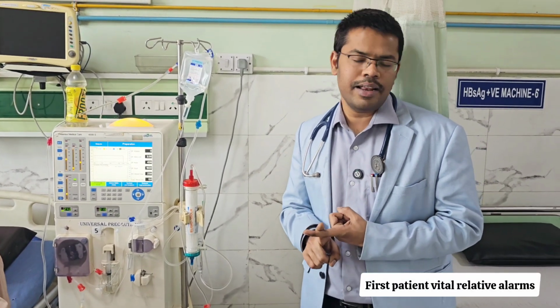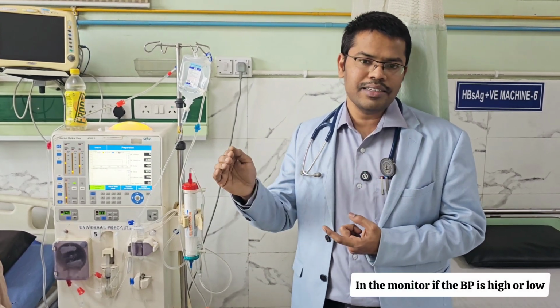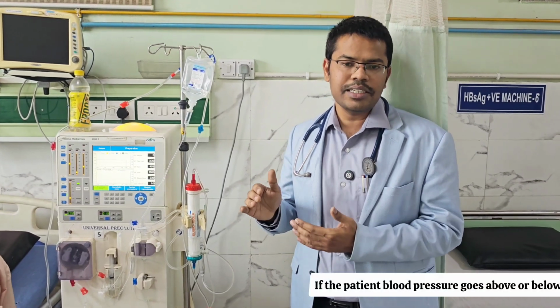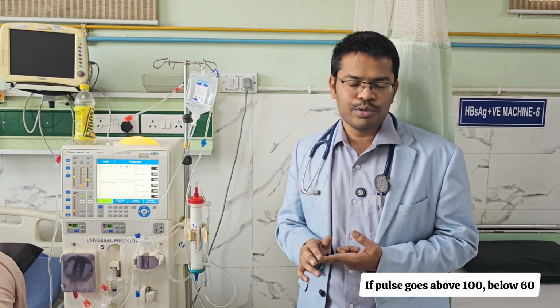So first, one by one, patient vital related alarms. In the monitor, if the BP is high or low, that you can set. For example, in most units we set the BP higher level as 180 and lower level as 90. If the patient's blood pressure goes above or below that, the alarm will ring, especially during the dialysis. Pulse also you can set. If pulse goes above 100 or below 60, the pulse alarm will ring. These are patient vital related.